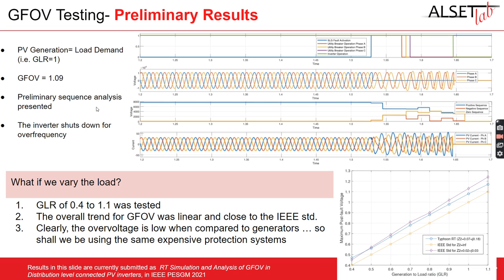What if we vary the load? Instead of just showing a result for a GLR of 1, we are showing a generation-to-load ratio of 0.4 to 1.1. We can see that the pattern of overvoltage at unfaulted phases very closely follows the IEEE standard. This further affirms our hypothesis that the overvoltage is definitely much less than for synchronous generators, and the behavior is somewhat different.